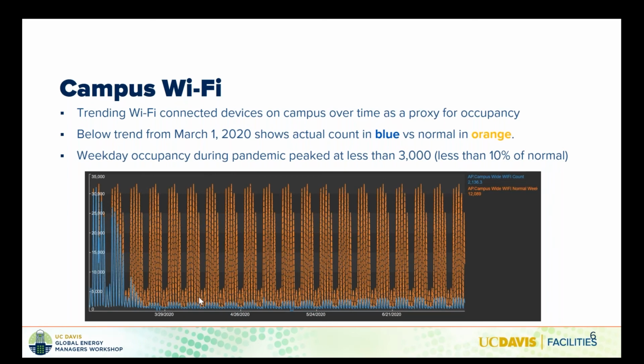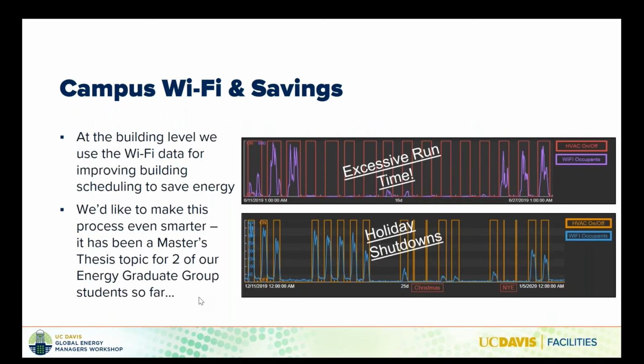We can see that trend at the building level too, and we use that data with our energy engineering team to optimize scheduling. The HVAC schedule is shown in red, on and off, and looking at the Wi-Fi data you can see many days in this building where HVAC systems are running with nobody in the building. So we're able to optimize scheduling - not yet in real time, though we are doing some real-time alerts - by programming weekly schedules based on typical occupancy rates, and the same for holiday shutdowns. We're still working on more we can do with this.